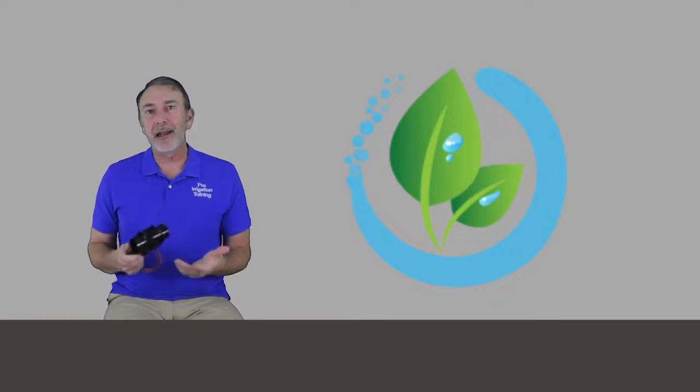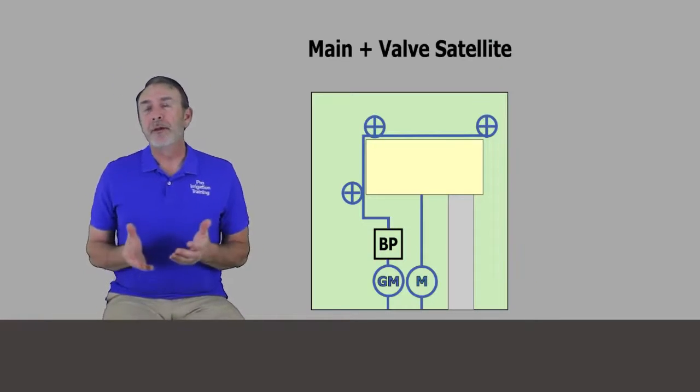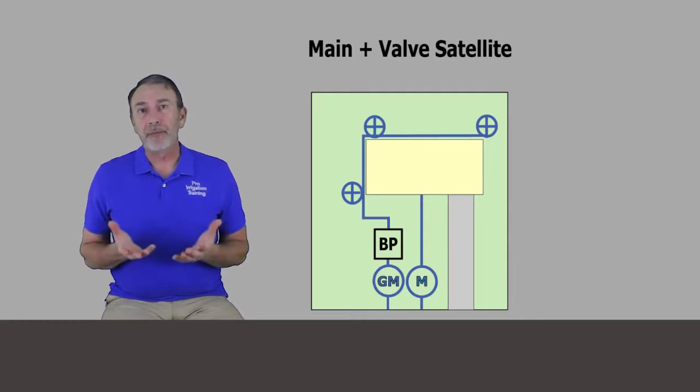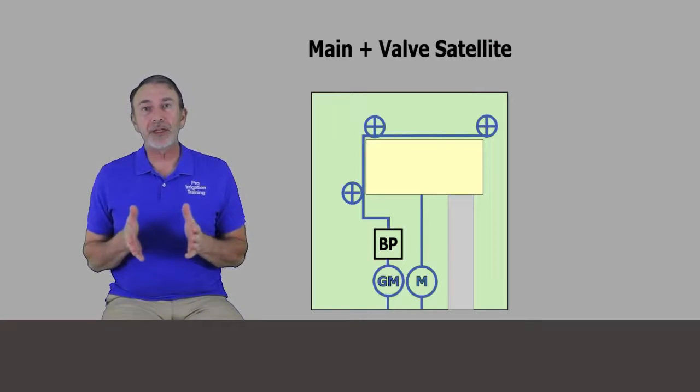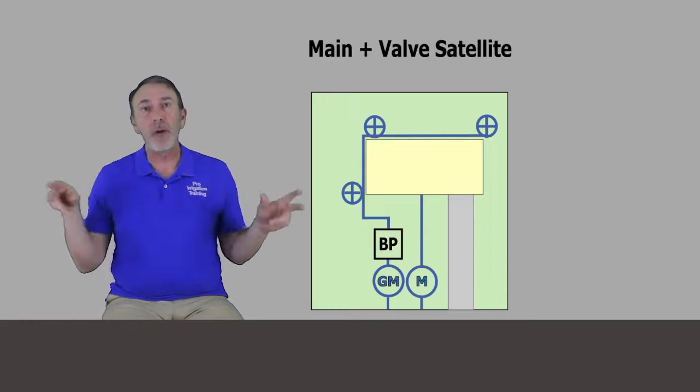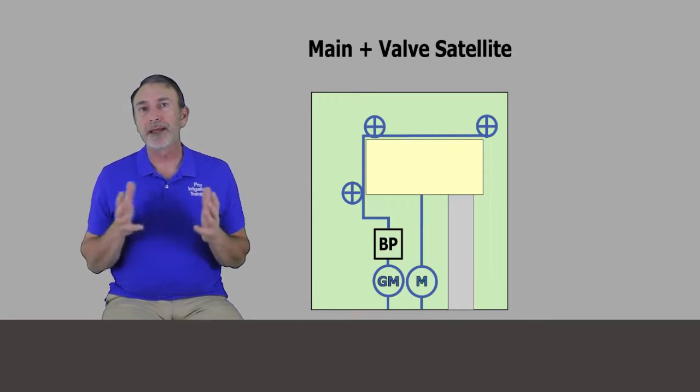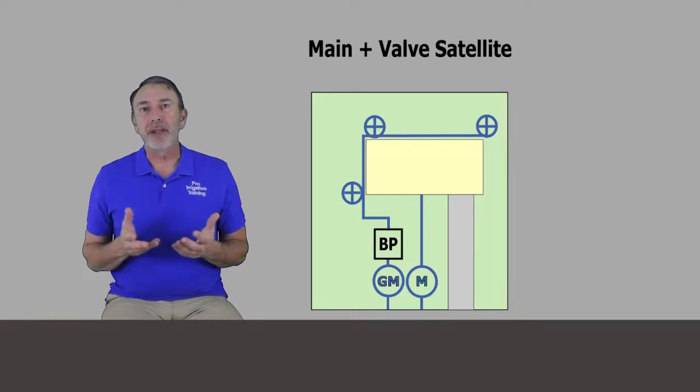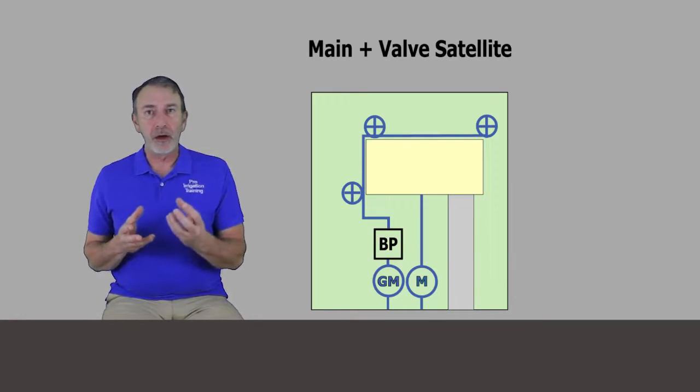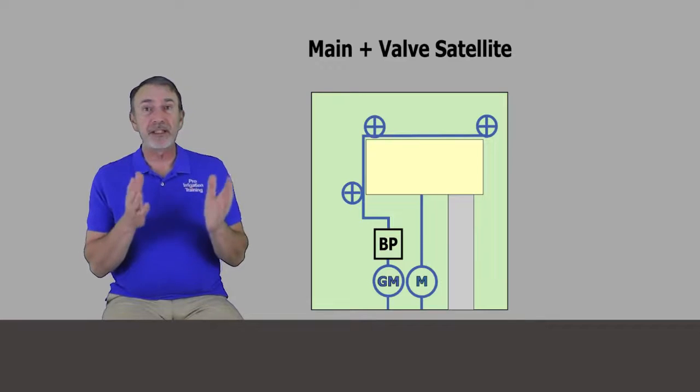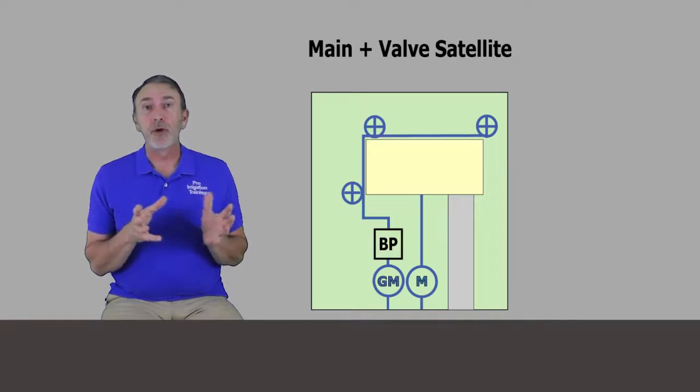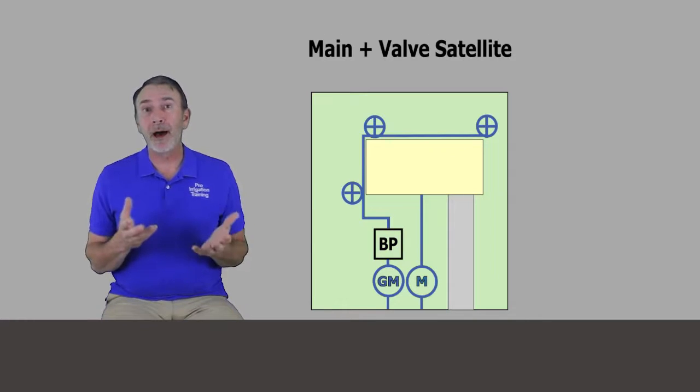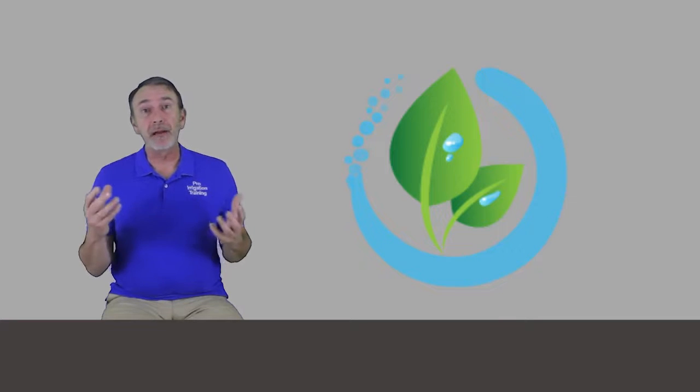Now we're going to talk about a satellite method. The manifold method is generally going to make you use more pipe, because you have a central location of the valves and then the pipes have got to go out to each zone. So you're going to use more pipe, but less wire. A satellite method is where we place one zone or one valve in the vicinity of the zone that it's servicing. So we're going to use less pipe, but more wire.